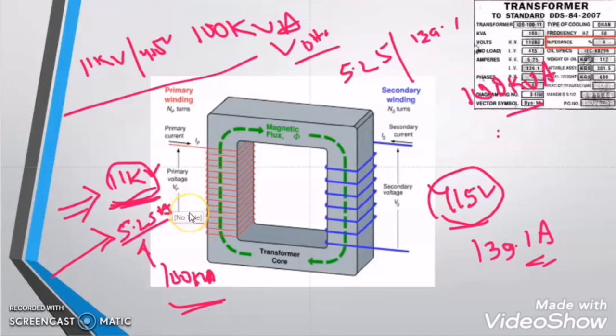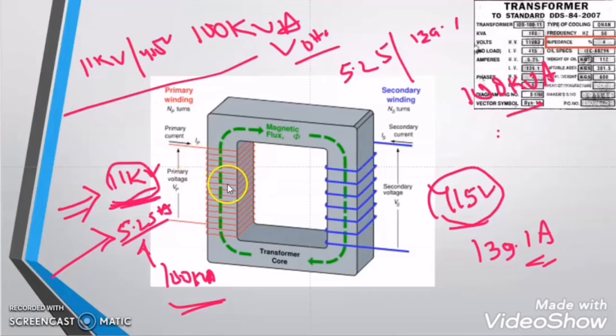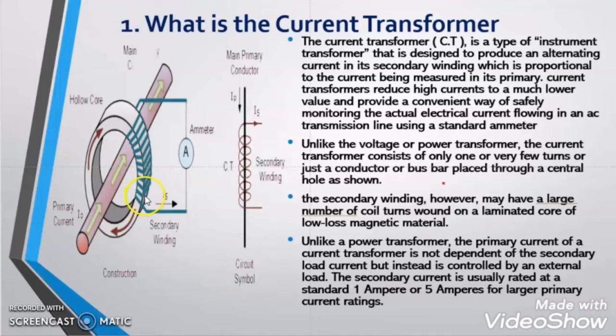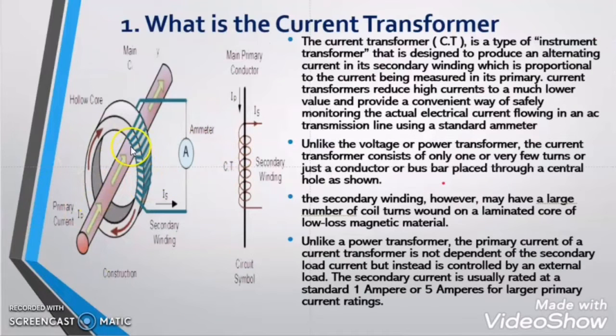An important question arises: are the power transformer and the current transformer the same? The answer is a big no. In the power transformer you will find two windings — one primary and one secondary. But in the current transformer you will find only the secondary winding. The primary winding of the current transformer is that conductor or bus bar whose current we need to measure.